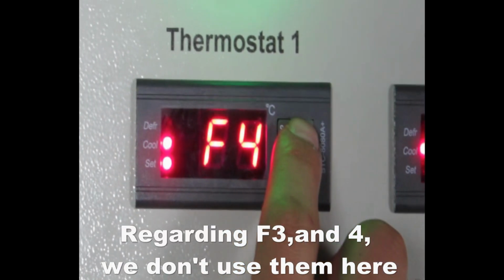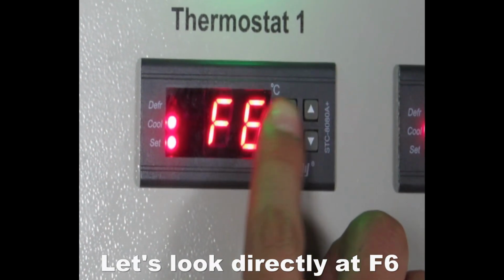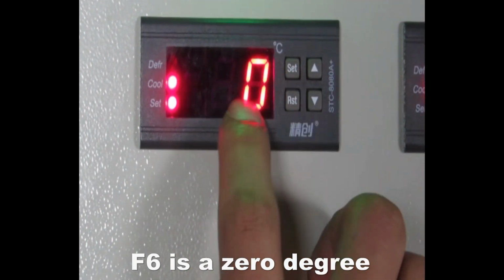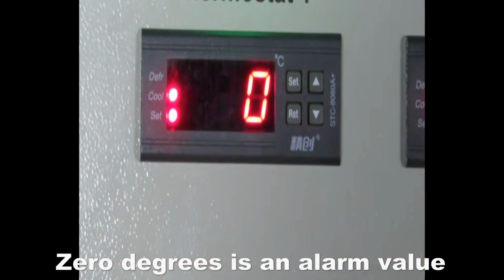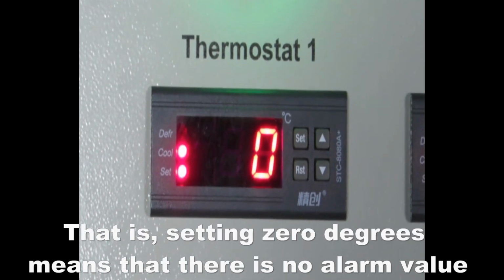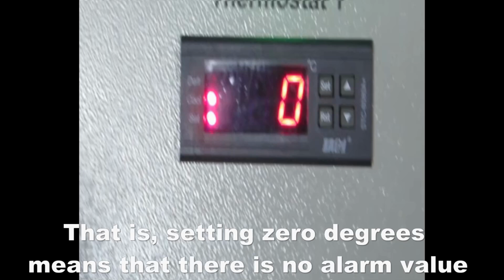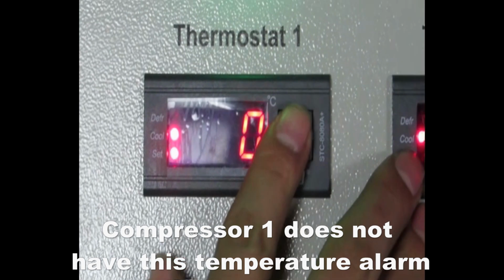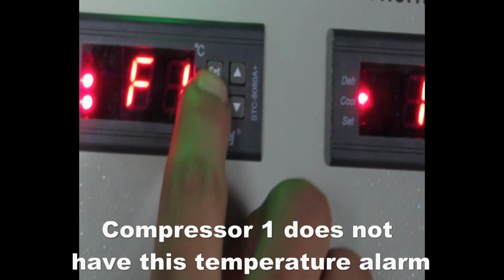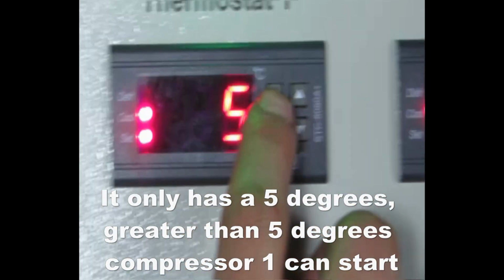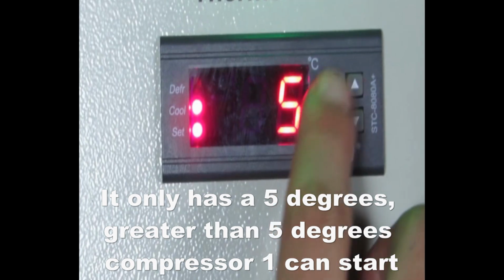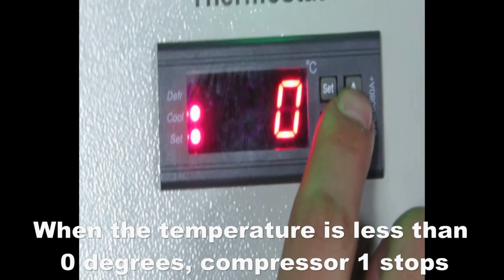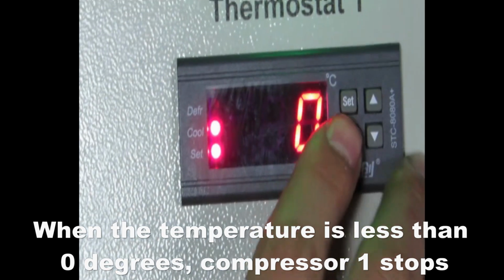Regarding F3 and F4, we don't use them here. Let's look directly at F6. F6 is 0 degrees. 0 degrees as an alarm value means there is no alarm value. Compressor 1 does not have this temperature alarm. It only has the 5 degrees: when the temperature is greater than 5 degrees, compressor 1 can start. When the temperature is less than 0 degrees, compressor 1 stops. This is the setting of thermostat 1.